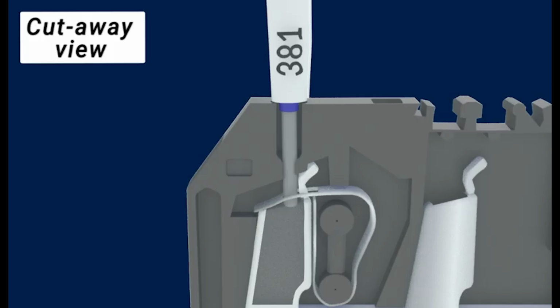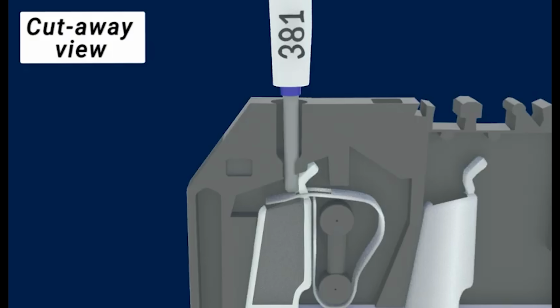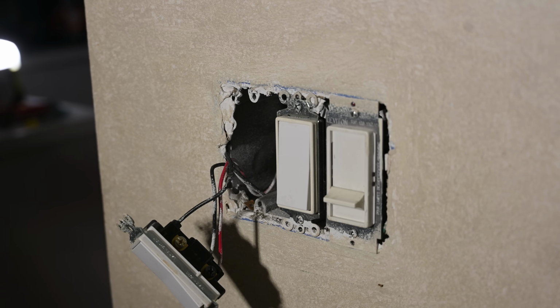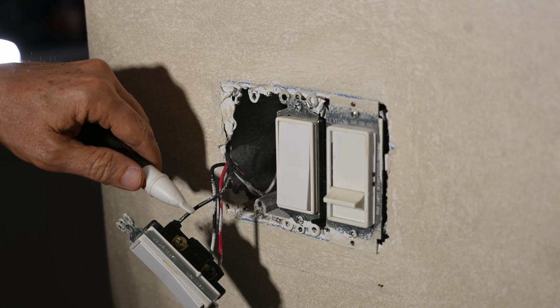So due to this loose, unstable connection, over time, the ferrule on wire 1 pulled out of the spring clamp to rest on top of the spring clamp face, resulting in a very precarious electrical connection. So when an arcing gap occurred between the ferrule and the spring clamp face, the electrical circuit was then interrupted, leading to the blackout of the Dali. So I've gotten called by numerous friends over the years because their outlet was working 1 minute and then not the next minute. So like the lamp is not working now, but it was working last night.